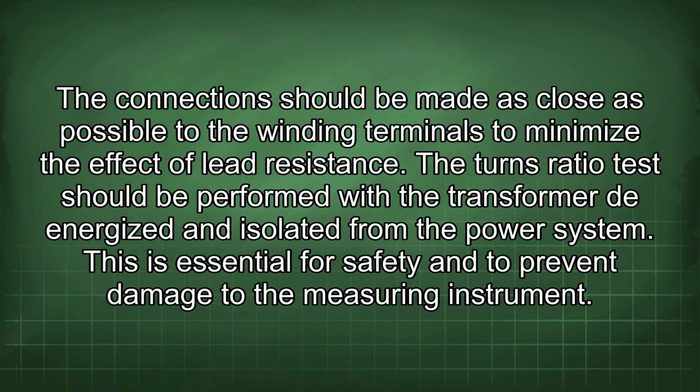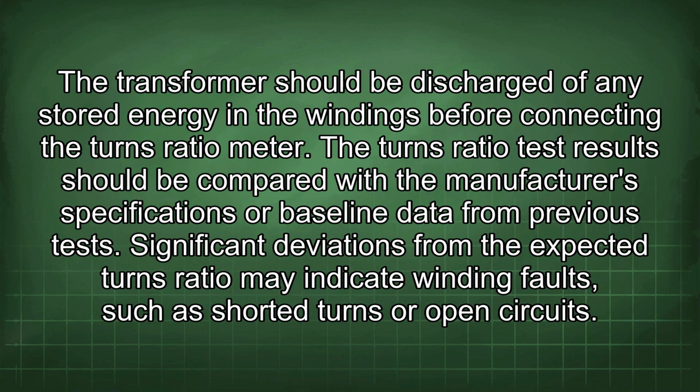The turns ratio test should be performed with the transformer de-energized and isolated from the power system. This is essential for safety and to prevent damage to the measuring instrument. The transformer should be discharged of any stored energy in the windings before connecting the turns ratio meter.